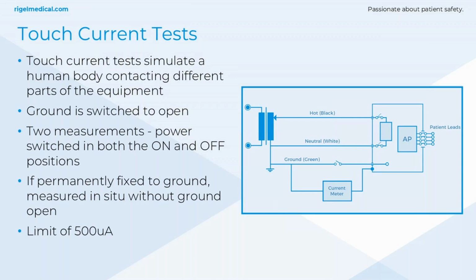What it's doing is just simulating a human body contacting different parts of the equipment, what the leakage current would be flowing through that person, and what's within acceptable limits. So for the touch leakage current test, the ground is always switched in the open position. Two measurements can be taken, so it depends if it has a power switch. If it's got no power switch, then it's just tested once. But if it comes with a switch, then it's tested in both the on and off positions.